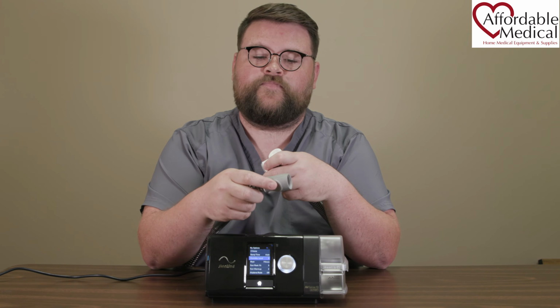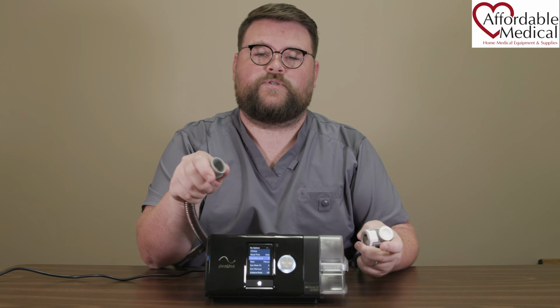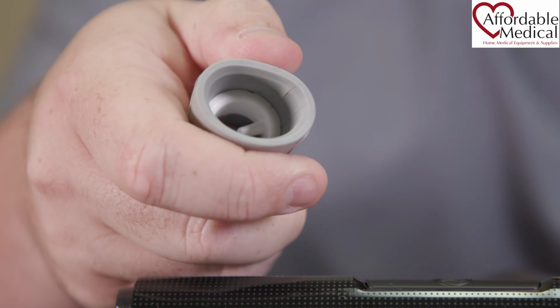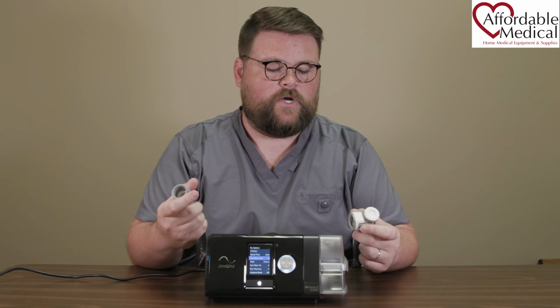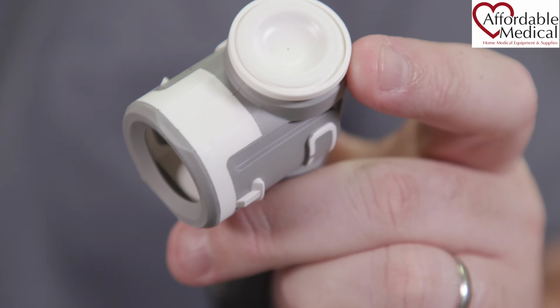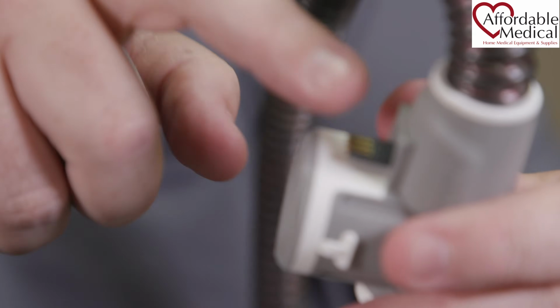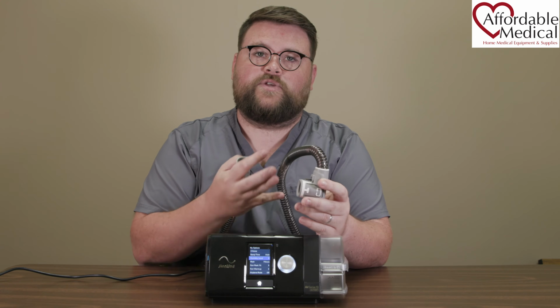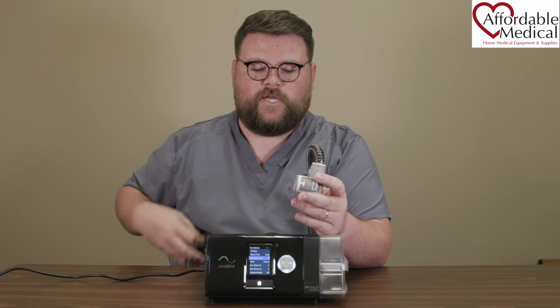The easiest way to check is it should slide on easy to the mask. If the fitting is stuck, you won't be able to squeeze the tubing. If you can squeeze it, it's ready to fit any home CPAP mask or BiPAP mask that you could own. On the other end of the tubing here, you actually have the connector that's going to allow the machine to recognize the tube in order to do that measurement.